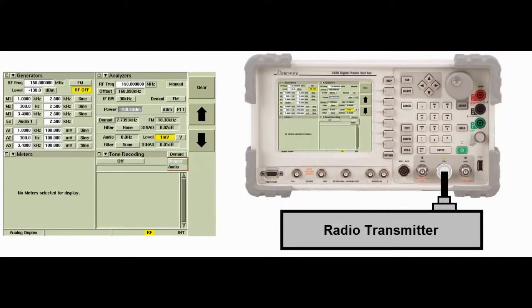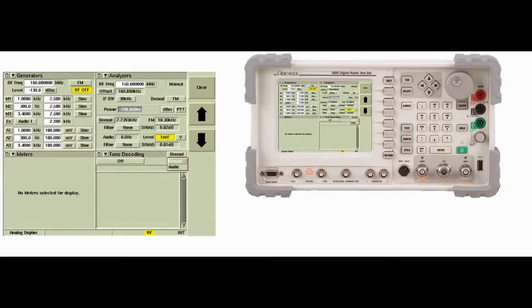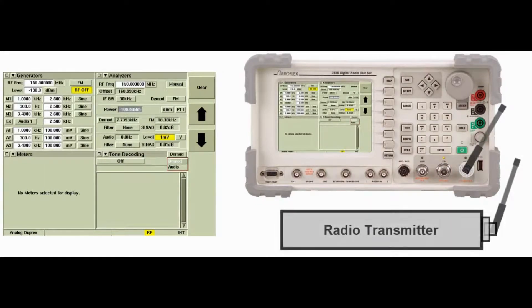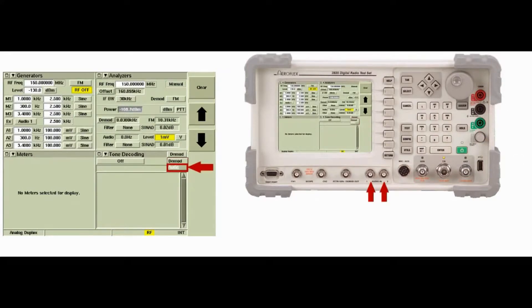The instrument can receive the signal directly from a transmitter through the TR connector. The signal can also be decoded off the air through the antenna connector. Selecting audio as the input allows the instrument to decode baseband signals applied to the audio input connectors.